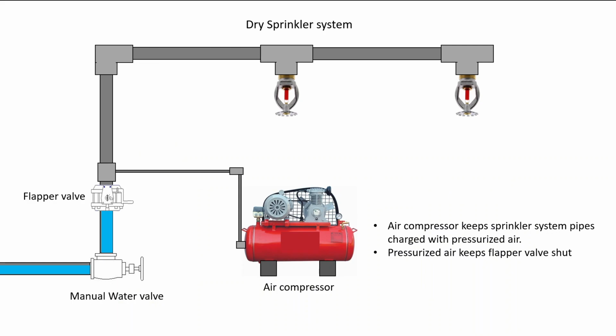The air compressor keeps the sprinkler system pipes charged with pressurized air, and the pressurized air keeps the flapper valve shut. It would be expected that the air compressor runs periodically throughout its lifetime, and that's because there will be small air leaks and air will simply slowly leak out of different areas of the pipe over time. So it's expected that this will kick on every so often.